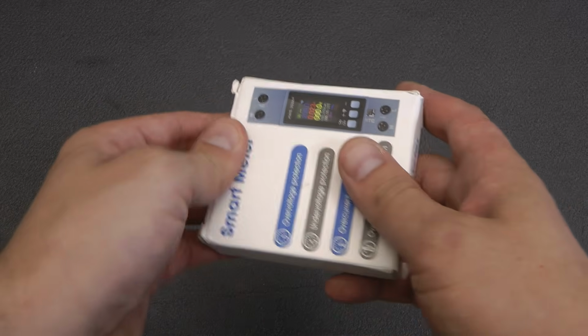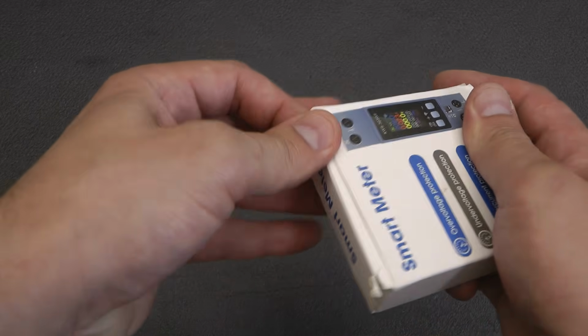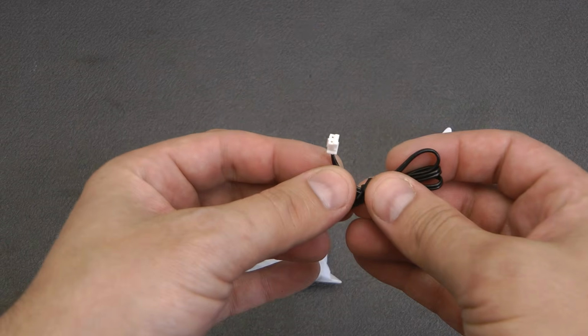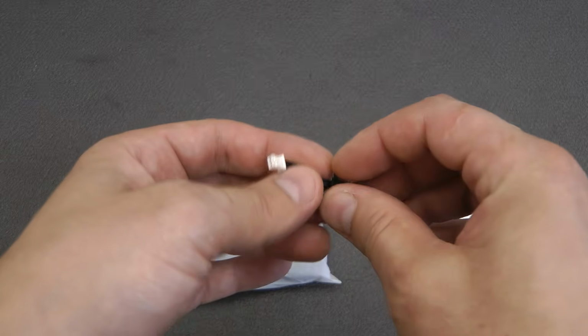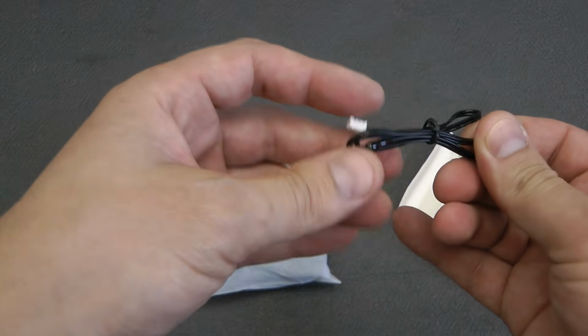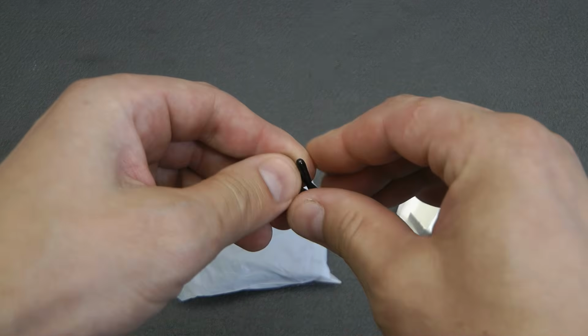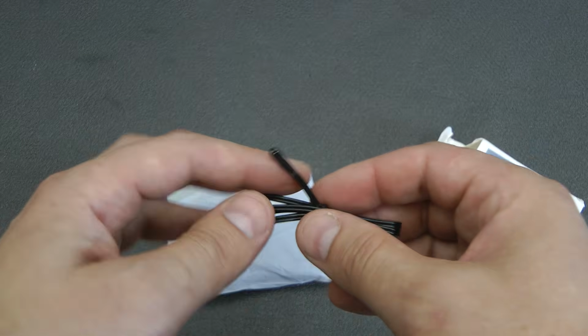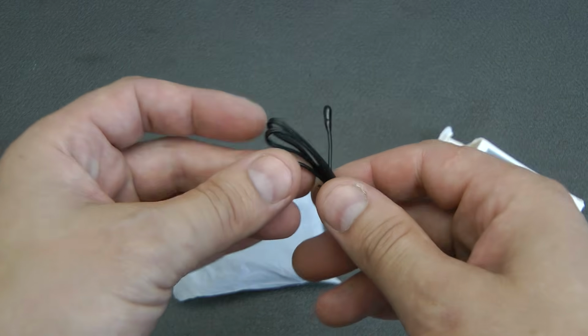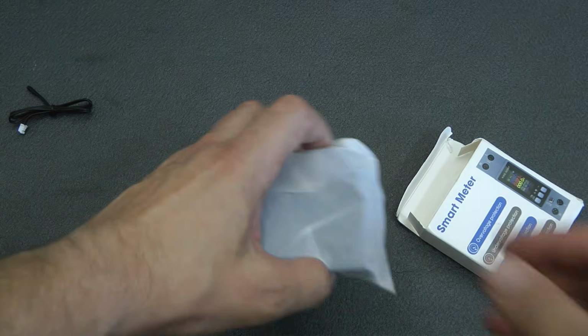The delivery damaged the box a little, but there is basically nothing inside that can break. The package includes the relay, the temperature sensor, and the instruction manual, which I have already managed to lose somewhere. The sensor connects to the relay with a 2-pin connector, and the cable length is 50 centimeters. It can be placed, for example, near circuit breakers, a contactor, or terminals inside the electrical panel, and you can configure the load to be switched off in case of overheating.